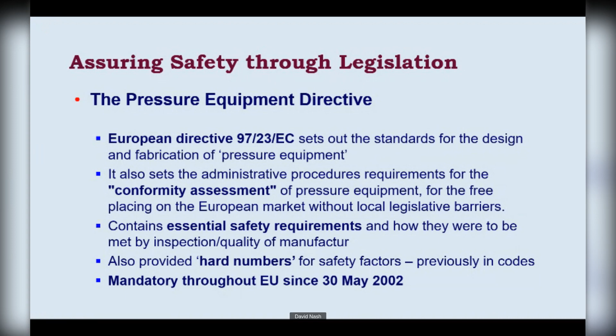It contains essential safety requirements and how they were to be met by inspection and quality of manufacture. Also, it provided some hard numbers, some safety factors, which were previously contained in design codes. And it has been mandatory throughout the EU since May 2002. Now, the British standard for pressure vessels isn't PD 5500, rather it's BS EN 13445. It still is called the European Code, but it is indeed the current British standard. And it automatically provides presumption of conformity.